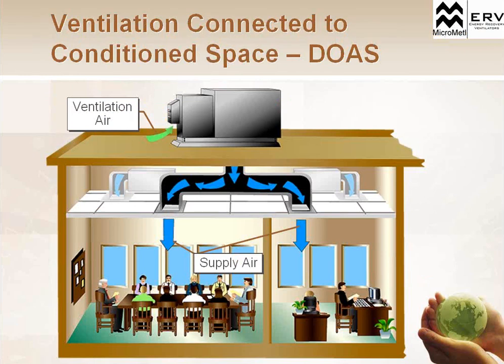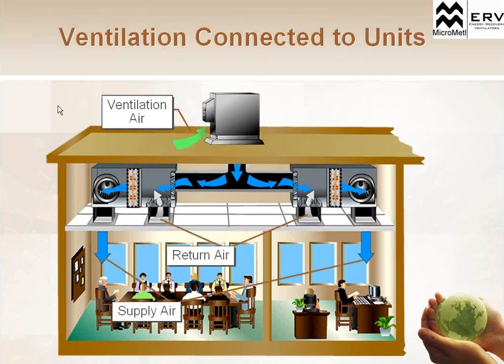There's a couple of different ways that we can duct this ERV air into the space. How do we get that outside ventilation air through the ERV and into the space? There are two main ways to do that. Basically, we can take the dedicated outside air approach, where we have our ventilation air coming in. This is our ERV system, taking that outside air directly into the space. Here's an energy recovery unit on a dedicated outside air system. We're fully tempering that outside air, preheating and pre-cooling it, and completely tempering the air to go directly into the space, separate from our HVAC system, decoupling our ventilation requirement from our space load requirement. In that instance, the HVAC system would just be maintaining the load requirement in each space.